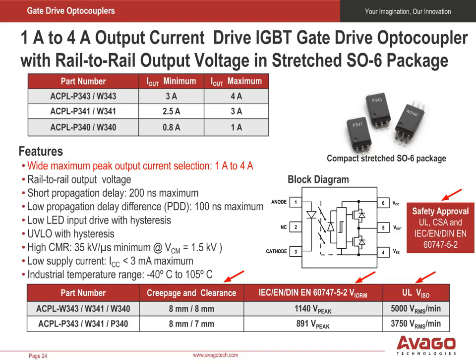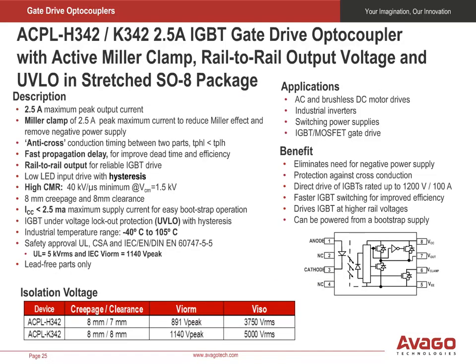All devices meet worldwide safety standards. The 2.5-amp drive ACPL-H342 and ACPL-K342 IGBT gate drive optocouplers include an active Miller clamp and under-voltage lockout protection. They feature rail-to-rail output voltage swing and are offered in a compact stretched SO8 package. Rail-to-rail output voltage swing is achieved by a delayed turn-on of an additional P-channel MOSFET in the device, removing the 2-volt drop after the first N-channel MOSFET is fully turned on. This ensures that the IGBT's gate voltage is driven to the optimum level, with no power loss across the IGBT, even when an unstable power supply is used.